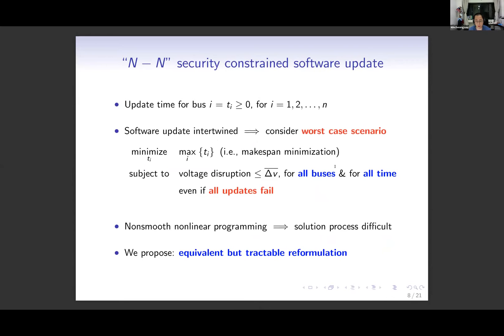We present the mathematical optimization model of our software update rollout problem. The objective is to minimize makespan. The N-N security constraint specifically means that even in the worst-case scenario where all updates fail, the total voltage disruption should not exceed the limits at all buses and at all times. This optimization problem is non-smooth and non-linear, which is difficult to solve directly. So we derive effective solution methodologies based on a reformulation.